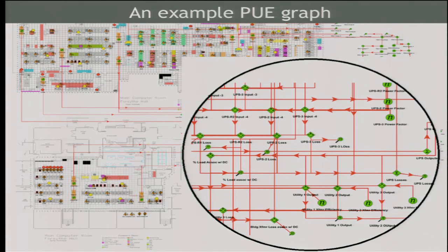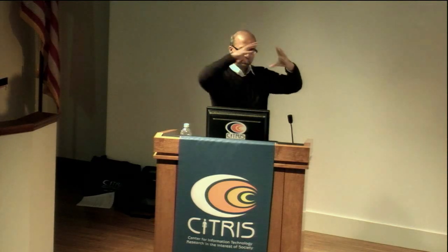But this graph allows you to go at any level, and you can assign any metric of power usage at any of these levels. So what you can do now is that once you have this graph, this how power flows through your entire data center, then you can start to use these metrics to see where your power is going and who is using how much power and what are the possible bottlenecks in this particular graph. So this can help you, again, optimize the power usage.